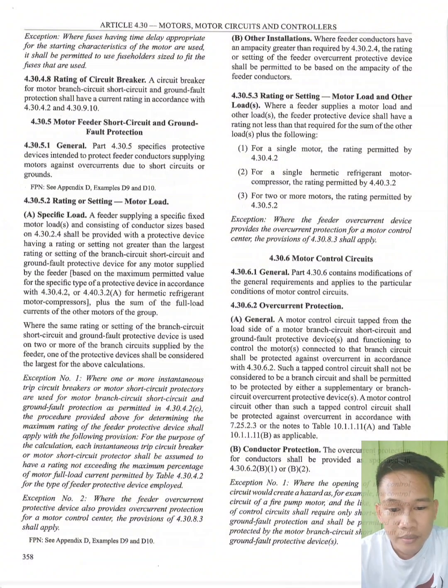Where the same rating or setting of the branch circuit, short circuit, and ground fault protective device is used on two or more of the branch circuits supplied by the feeder, one of the protective devices shall be considered the largest for the above calculations. So, now the exception. The first exception is where one or more instantaneous trip circuit breakers or motor short circuit protectors are used for motor branch circuit, short circuit, and ground fault protection as permitted in 4.30.4.2 C.